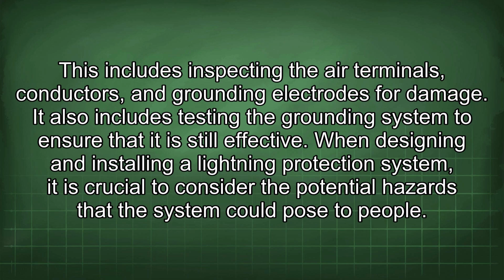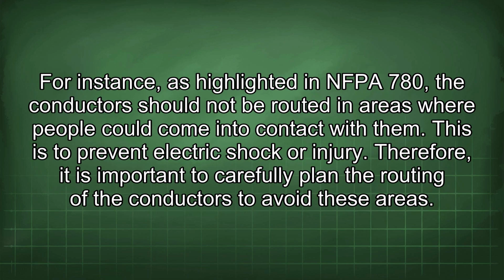When designing and installing a lightning protection system, it is crucial to consider the potential hazards that the system could pose to people. For instance, as highlighted in NFPA 780, the conductors should not be routed in areas where people could come into contact with them. This is to prevent electric shock or injury. Therefore, it is important to carefully plan the routing of the conductors to avoid these areas.